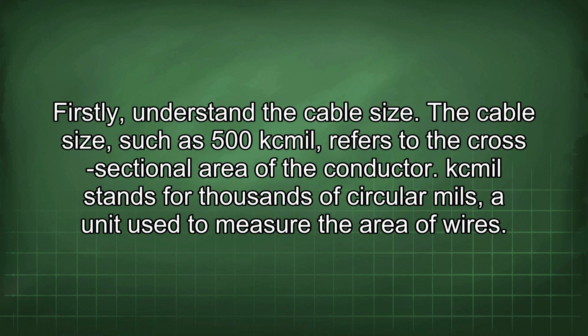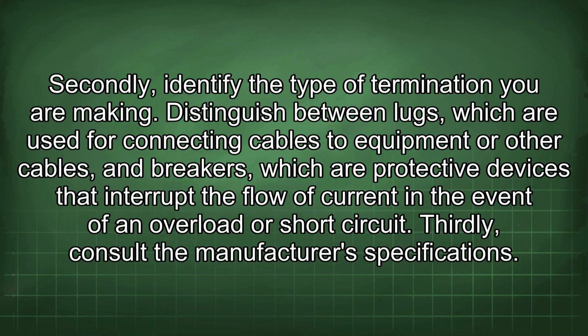Firstly, understand the cable size. The cable size, such as 500 kcmil, refers to the cross-sectional area of the conductor. Kcmil stands for thousands of circular mils, a unit used to measure the area of wires. Secondly, identify the type of termination you are making. Distinguish between lugs, which are used for connecting cables to equipment or other cables, and breakers, which are protective devices that interrupt the flow of current in the event of an overload or short circuit.